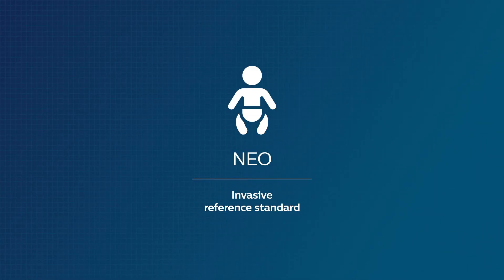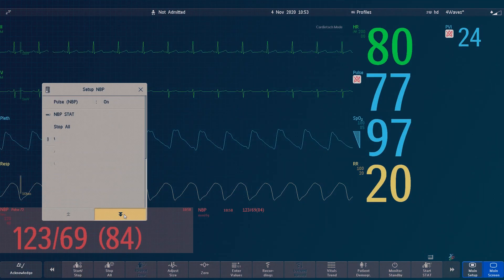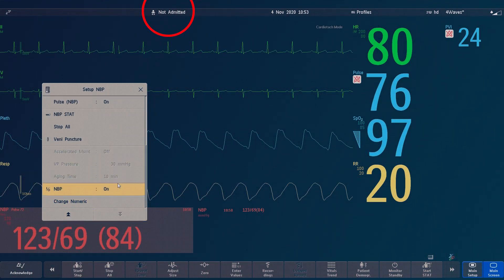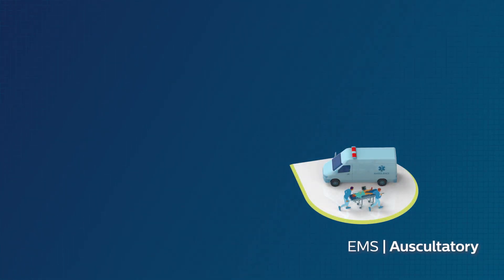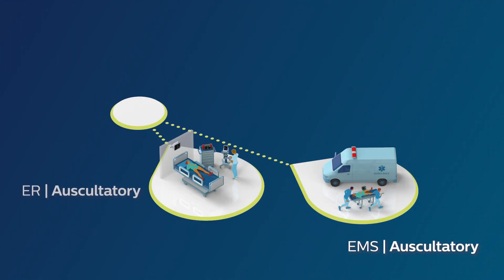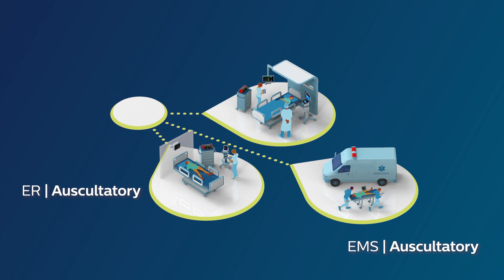As a reminder, the invasive reference standard is always used for the neonatal category and will not be visible in the menu when it's selected. Please note that the reference can be identified but not changed while in monitoring mode. If you encounter inconsistent configuration across or within your clinical unit or department, please contact your clinical leadership team.